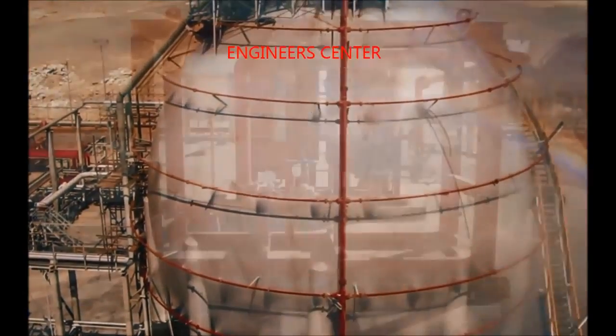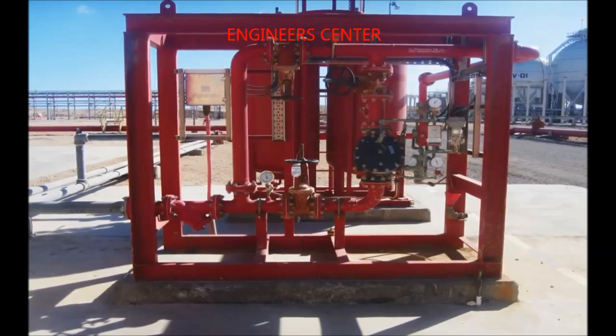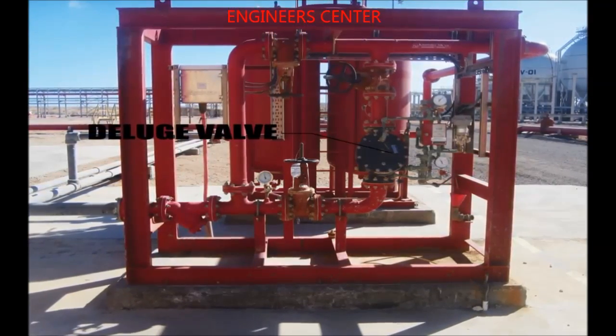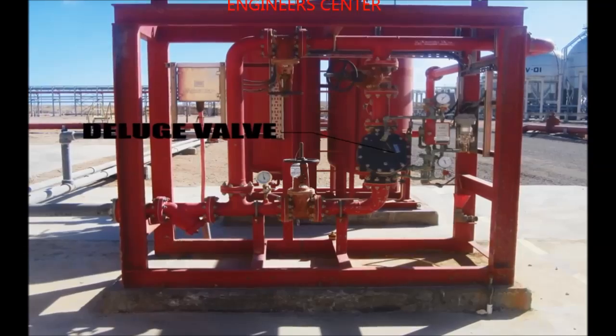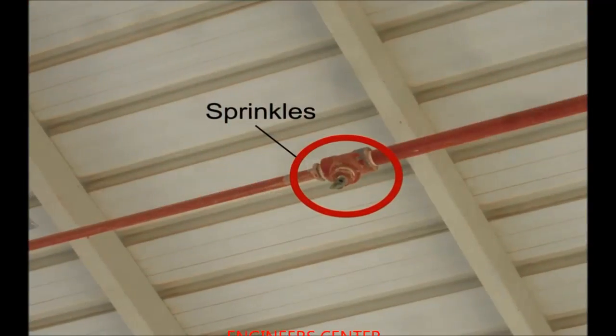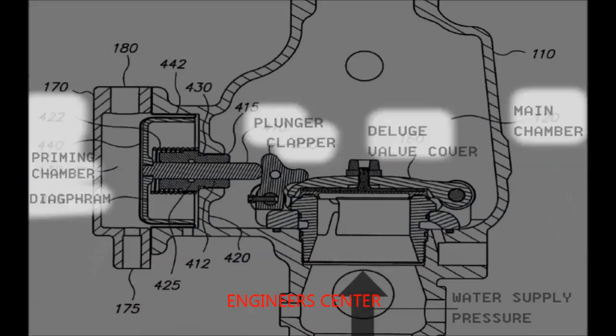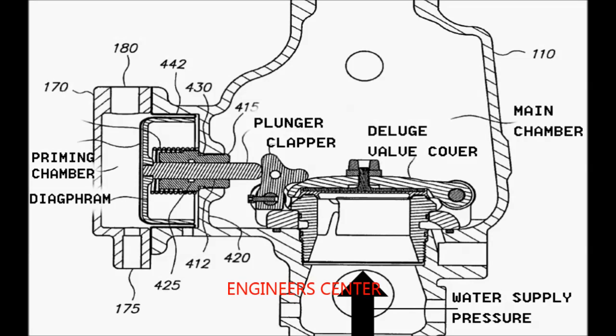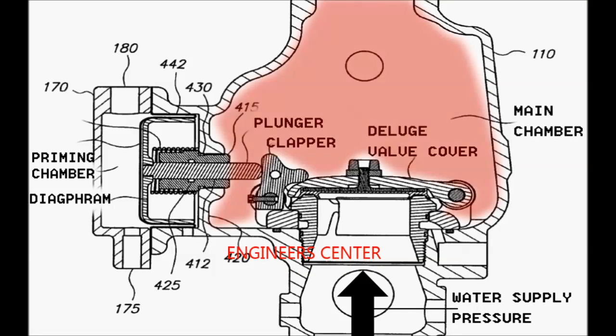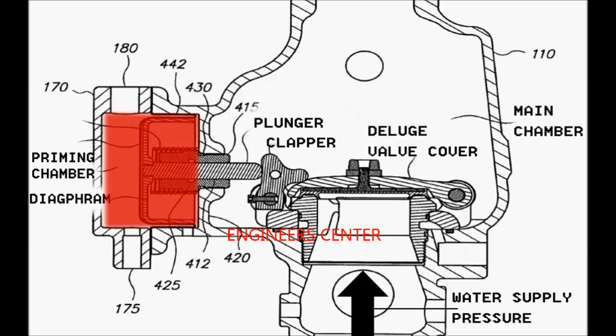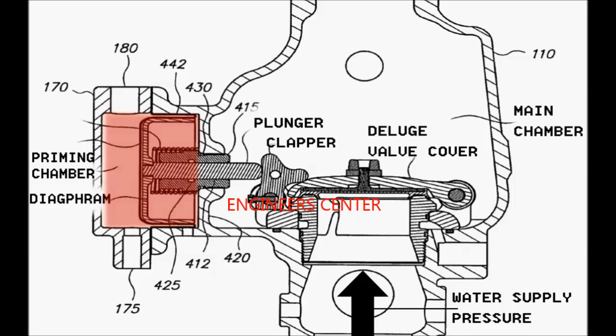The deluge fire protection system depends on the presence of a deluge valve that controls the flow of highly pressurized fire extinguishing fluid to the sprinklers or nozzles when a temperature element senses high temperature on the protected equipment. The deluge valve consists of two chambers: a main chamber, in which there is the motion of opening and closing the deluge valve, and the priming chamber — also referred to as the sensing chamber — in which there is the motion of the diaphragm responsible for opening and closing the deluge valve.